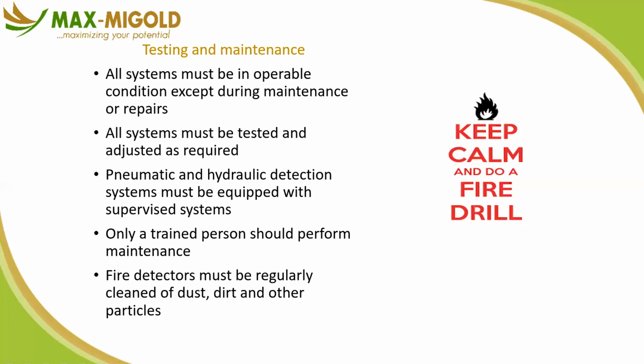We are facility managers. Even if the building is new, it doesn't matter—smoke detectors need to be inspected by competent persons every six months. We check functionality from the panel, and we visually inspect that there's no damage to the panel, the smoke detectors, the call bell, the sounder, and so on.